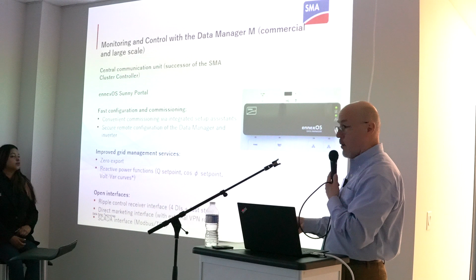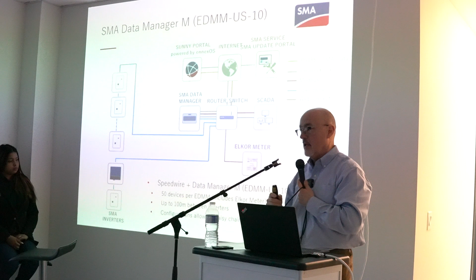Alex could speak much more eloquently to this than I can. Typical configuration with the data manager, a single data manager will support approximately 50 inverters. The integrated functionality we're going to be offering in our new inverters is a scaled down version of this, and it'll support approximately 5 inverters.